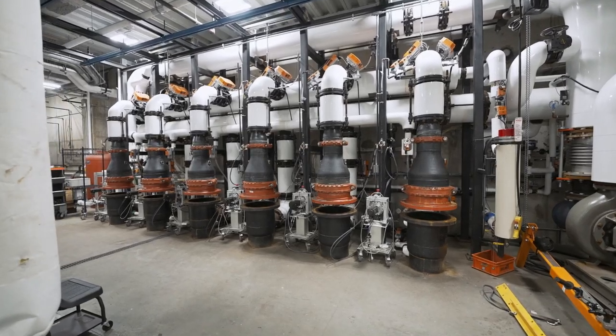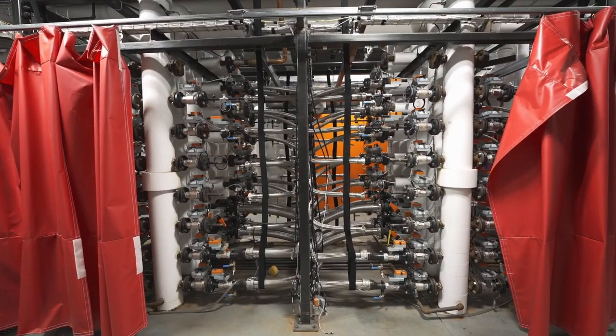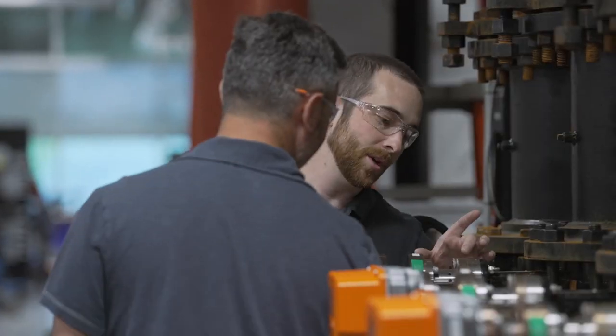Let's take a look at how these operate. Hey, Jeff and Tranquillo, are you there? Hello, and welcome to the Verification Center for Water located in Danbury, Connecticut. This is Jeff and Tranquillo, and we're both part of the IVQ team — IVQ stands for Innovation Verification Quality. Here in Danbury, we have a 15,000 square foot facility where we can do performance and lifecycle testing on our valves. For lifecycle testing, we typically take a control valve from 0 to 100,000 cycles at minimum and maximum temperature at a constant differential pressure. Our rigs can hold up to 240 different sizes of valves, managing anything between the DN10 and the DN450 in size.